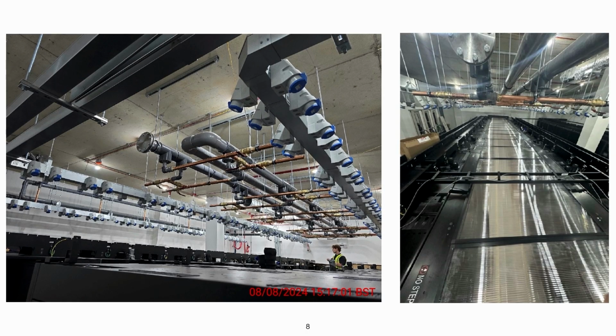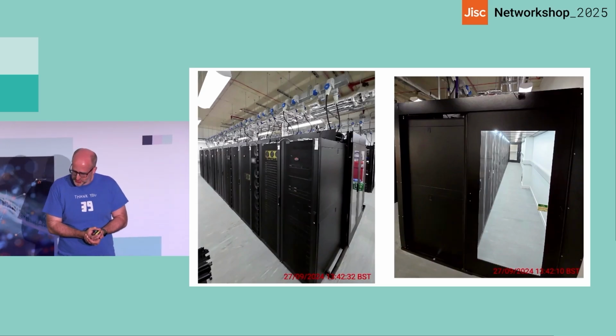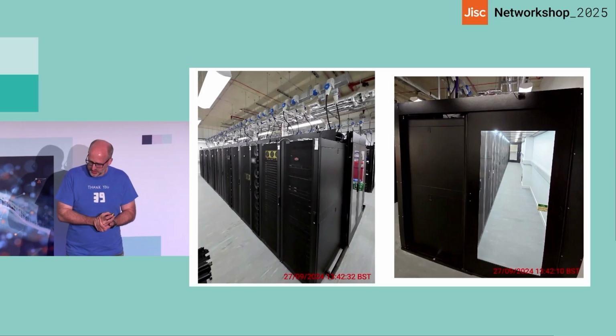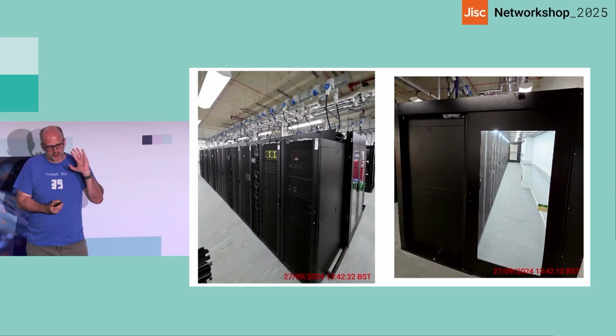A better picture there, just showing exactly what it is. So this is taken before the cooling was lagged. So the cooling pipes get lagged to protect them. And then this plot shows on the day we were commissioning the rack. So you can see at the top the lagged pipes. And if you notice the yellow fans in one of the racks, that's a heater. So we basically had a 200 kilowatt artificial load in the room to commission and make sure everything was working to that level. It wasn't possible to get all 390 kilowatts in one go. So that was in the room.